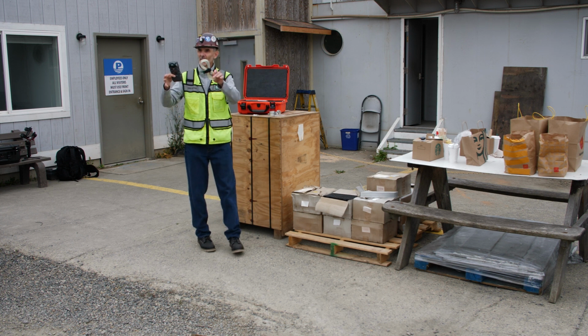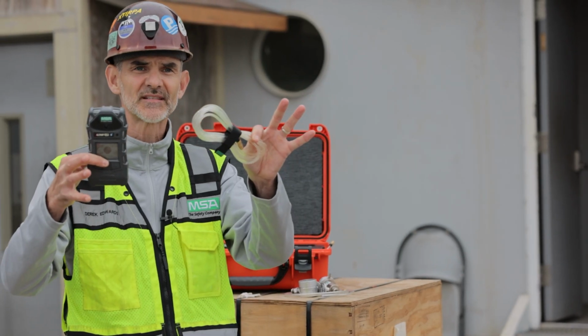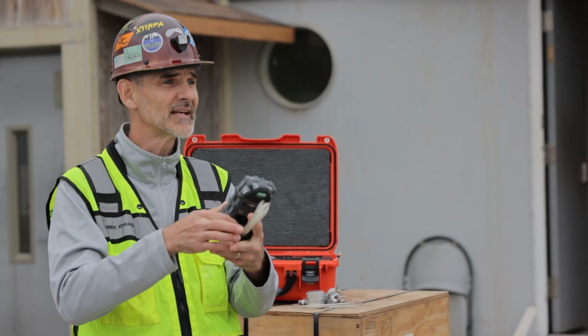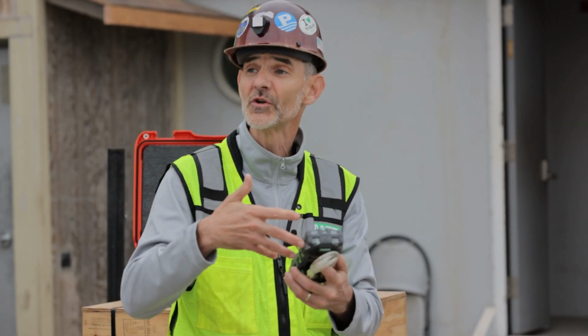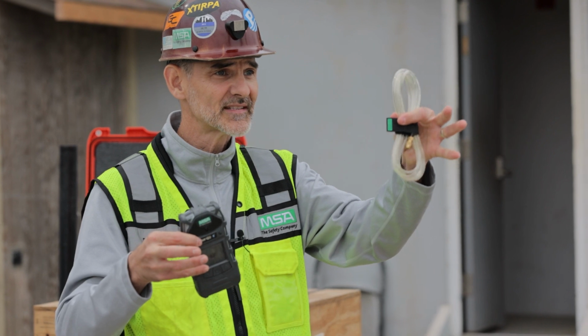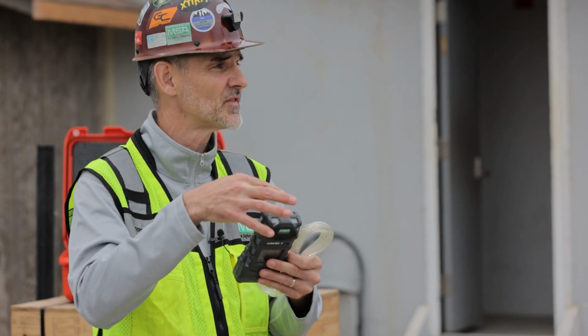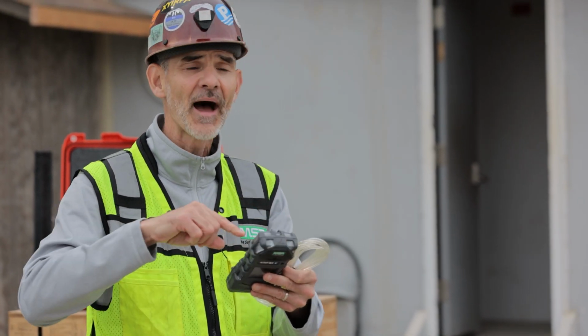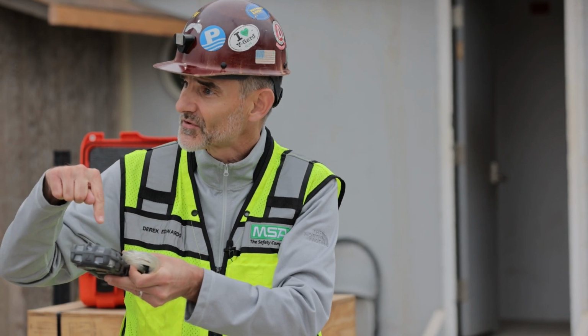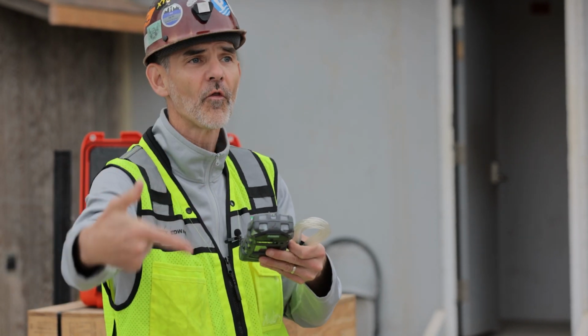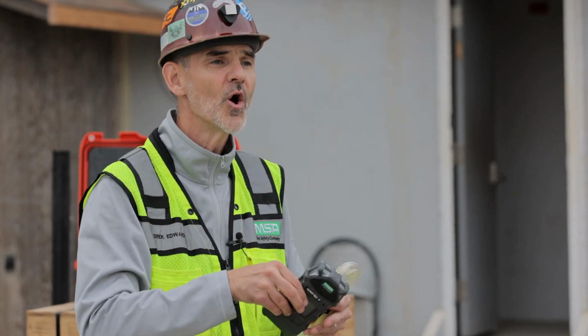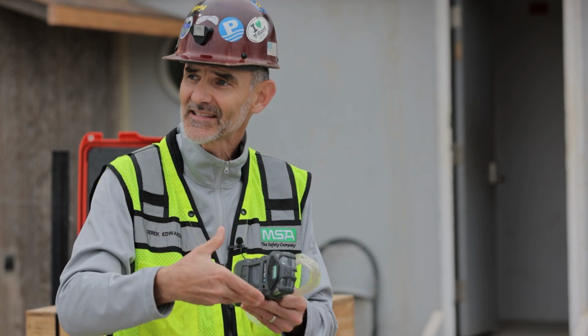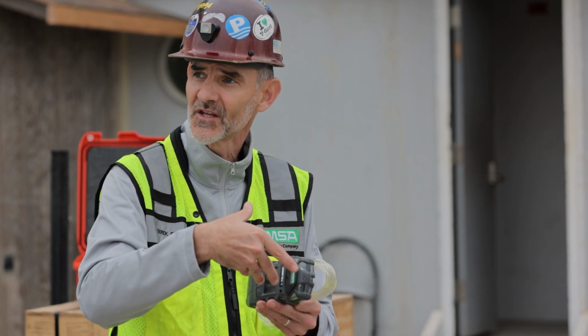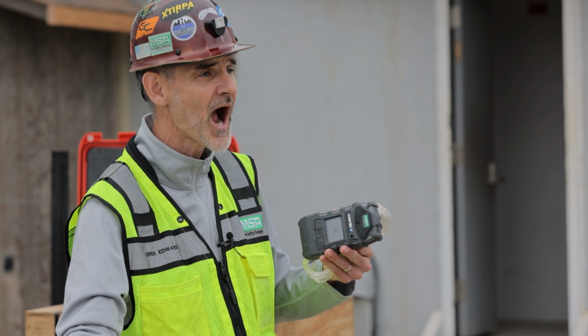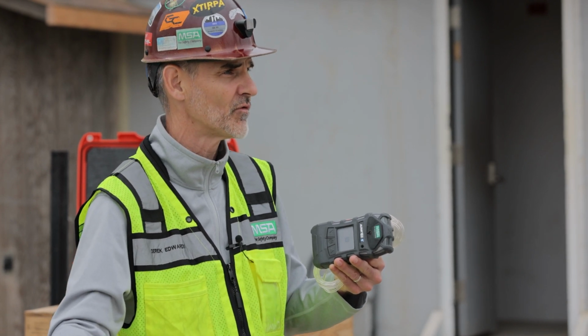In a little bit, I'm going to talk about the sample line and probe. I'm going to connect all of this up. If we're pulling a sample, which typically you're going to pull with the sample line and probe connected to the instrument, that means that your sample system goes from this pump all the way to the end of the probe, which means we need to connect that system before we start the instrument, and we're going to block the end of that probe, and I'll show that to you.